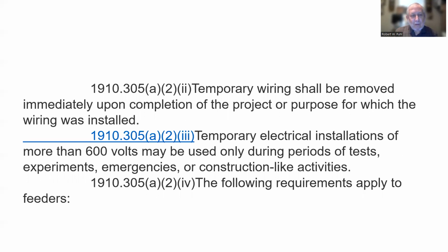Temporary wiring shall be removed immediately upon completion of the project or purpose for which the wiring was installed. And that makes great sense. Temporary electrical installations of more than 600 volts may be used only during periods of tests, experiments, emergencies, or construction-like activities. So that's in temporary installations of more than 600 volts. Now this is still A2.